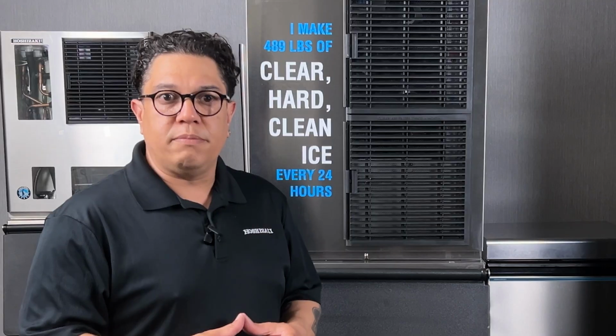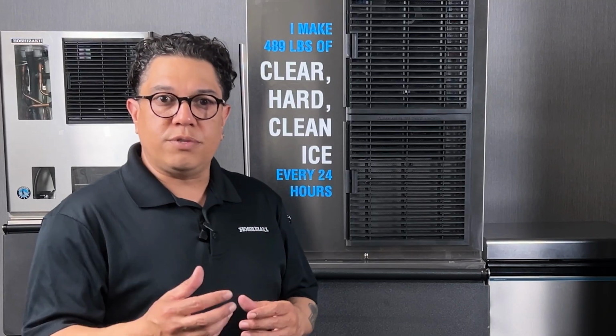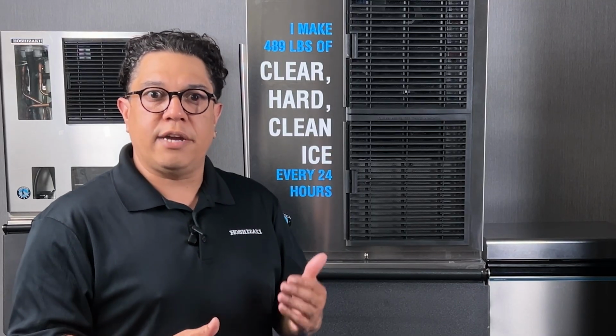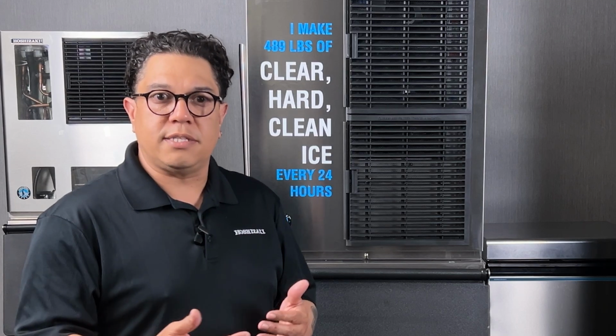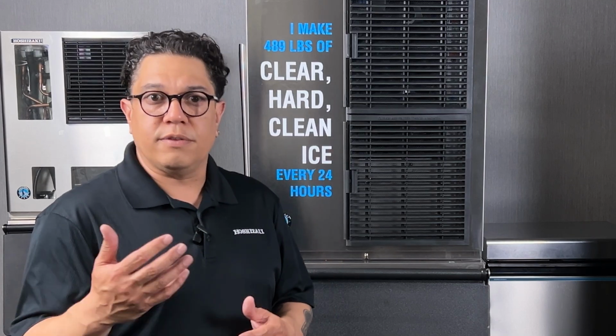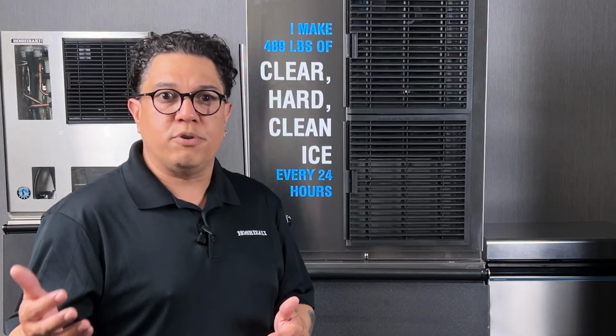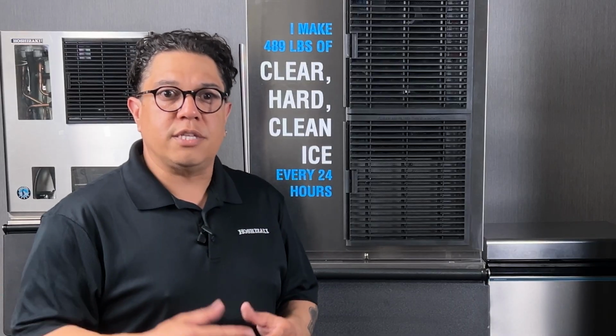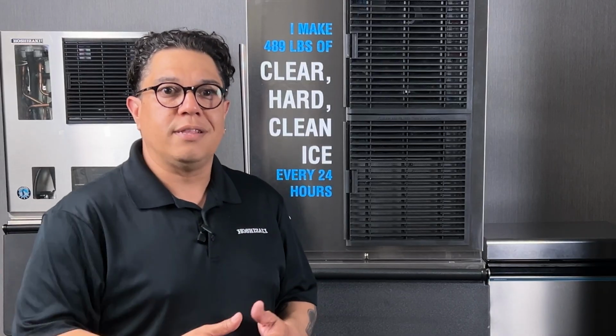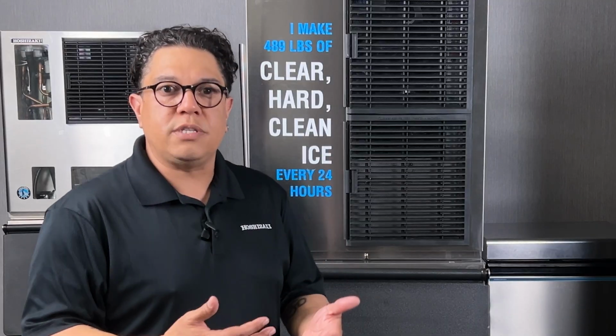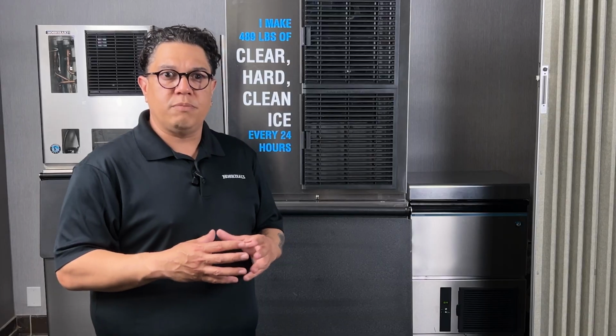The 7 beep alarm is a high voltage alarm. If the voltage coming into the transformer is higher than 115, like let's say it's 130, then the transformer is not capable of pushing out 10.5 volts. It's going to push out something a little bit higher, like 13, maybe 14 volts. So when you have this alarm, first thing we need to do is confirm the voltage at the board on the K2 connector. Then we're going to check the voltage going into the transformer. And that's how we're going to correct the problem.